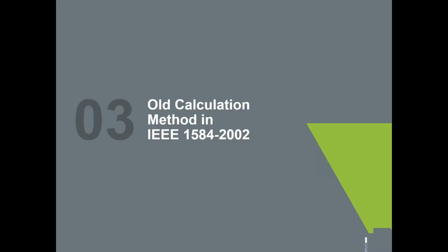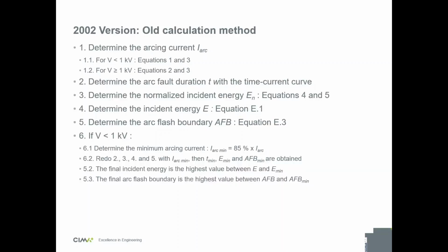So let's start by showing you the old equations in the 2002 version. The method itself: you start by finding your arcing current. Basically, the first step of an arc flash study is you draw your time current curves, you calculate your fault current, and then this is what was applied before. First, calculate your arcing current. Then you put your arcing current on the time current curve. You find your trip time. Then you calculate your normalized energy. Then you denormalize your energy with the working distance and the arc fault duration. Then you find the arc flash boundary.